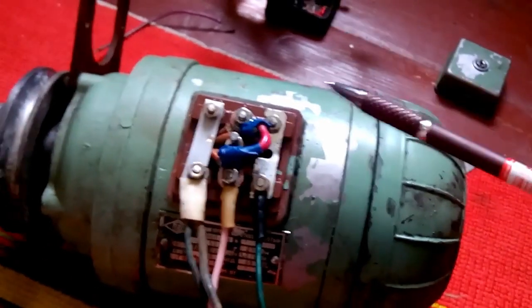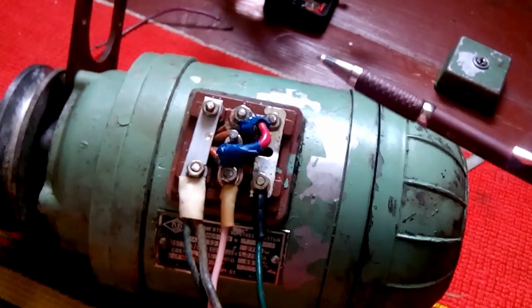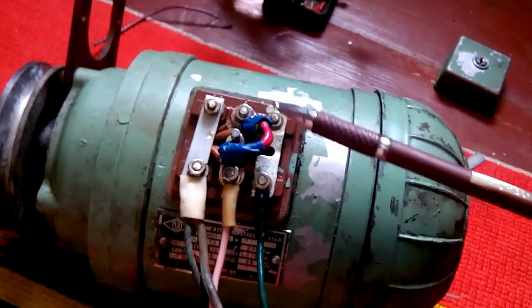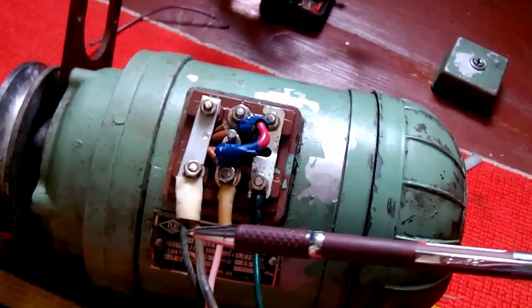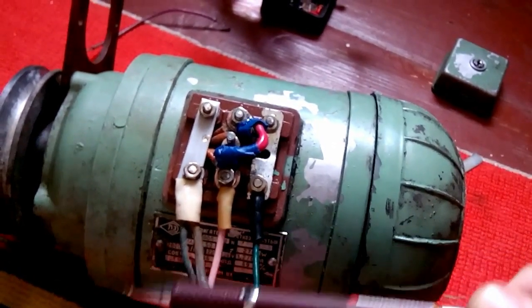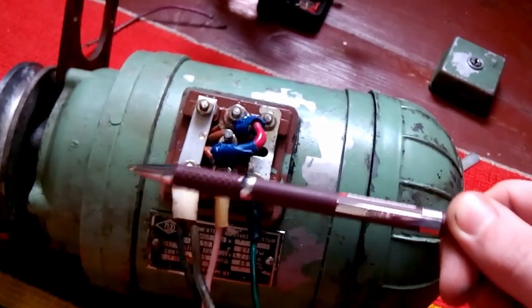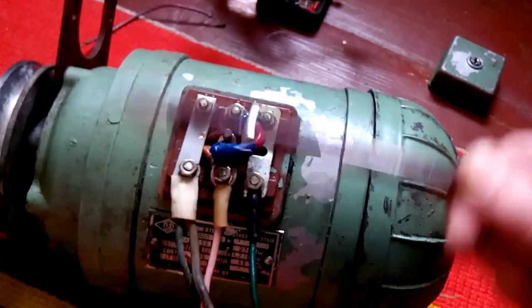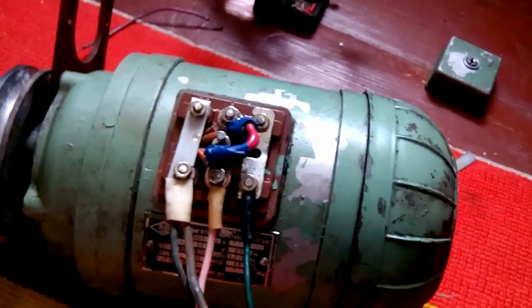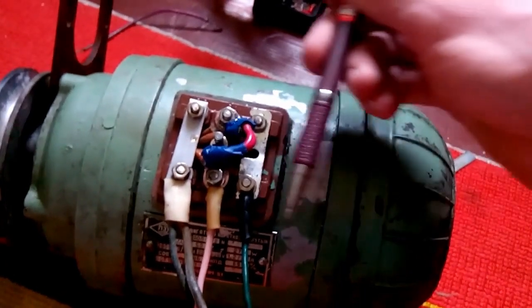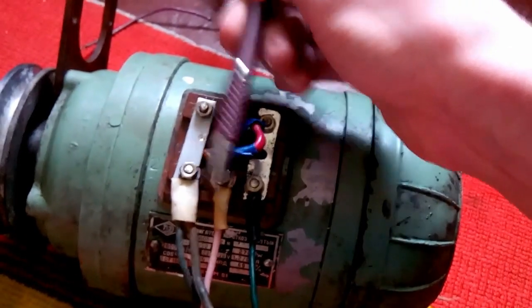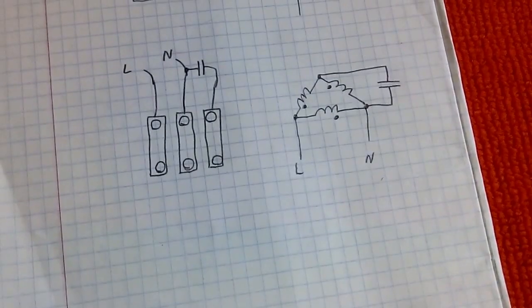All motors that I've seen essentially have such a configuration that for a three-phase supply, they have a bar shorting these three together or these three together. For a single supply, you need to short this one with this one, this one with this one, this one with this one. That's what this picture is for.